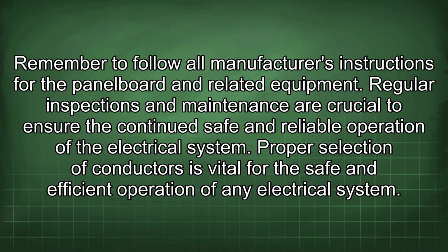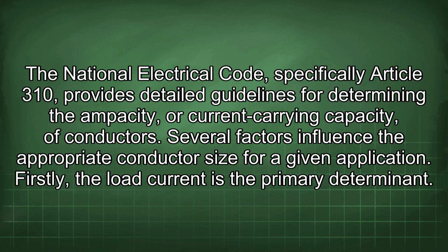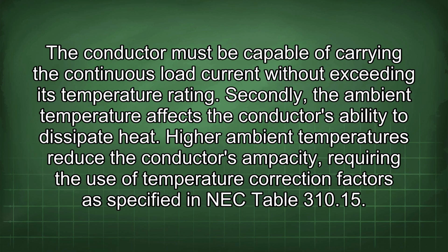Proper selection of conductors is vital for the safe and efficient operation of any electrical system. The National Electrical Code, specifically Article 310, provides detailed guidelines for determining the ampacity or current carrying capacity of conductors. Several factors influence the appropriate conductor size for a given application. Firstly, the load current is the primary determinant. The conductor must be capable of carrying the continuous load current without exceeding its temperature rating.